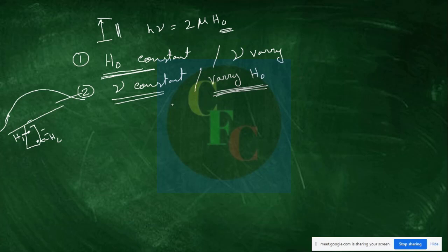Now see, the most important thing in nuclear magnetic resonance is the magnet itself. The magnet itself is the most important thing. First thing, as I said, the field has to be homogeneous, right? Inhomogeneity will bring out broadness of lines.